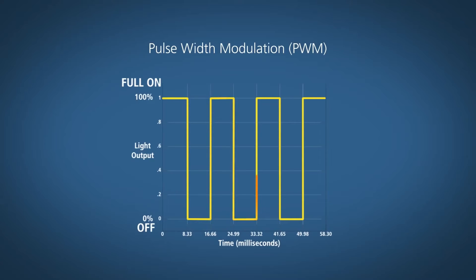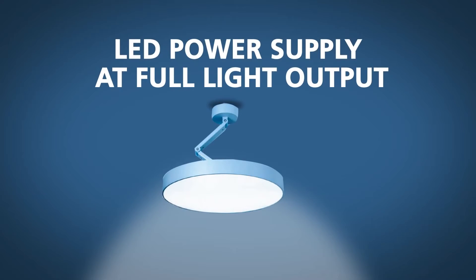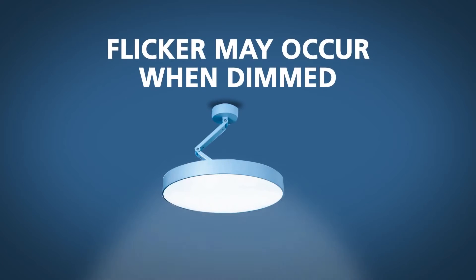This is similar to the way PWM adjusts the flow of electrons to the LEDs. CCR and PWM power supplies drive LEDs in a similar manner when full on — their differences only become apparent when dimmed. Observing an LED power supply under full light output may not expose you to objectionable flicker. This may occur, however, when the LED luminaire is dimmed.